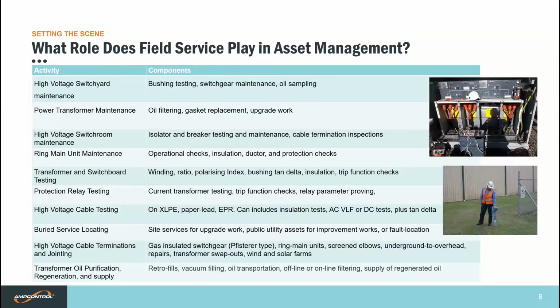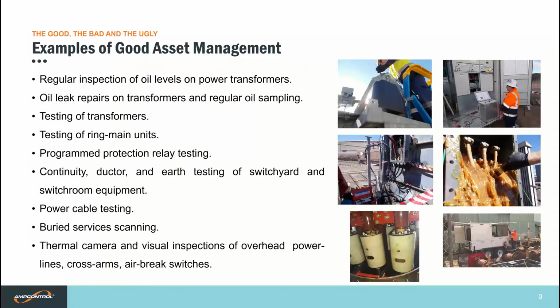Transformer oil purification, regeneration and supply. We can do retro fills, vacuum filling, oil transportation, offline or online filtering, or supply of regenerated oil. Some good examples of good asset management: regular inspections of oil levels on power transformers, oil leak repairs on transformers, and regular oil sampling, testing of transformers, testing of ring main units, program protection relay testing, continuity, ductor and earth testing of switchyards and switch room equipment, power cable testing, buried services scanning, thermal camera and visual inspections of overhead power lines, cross arms and air break switches.